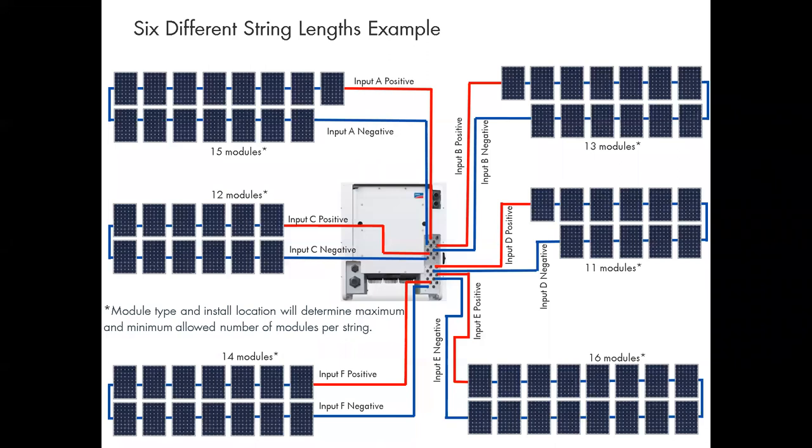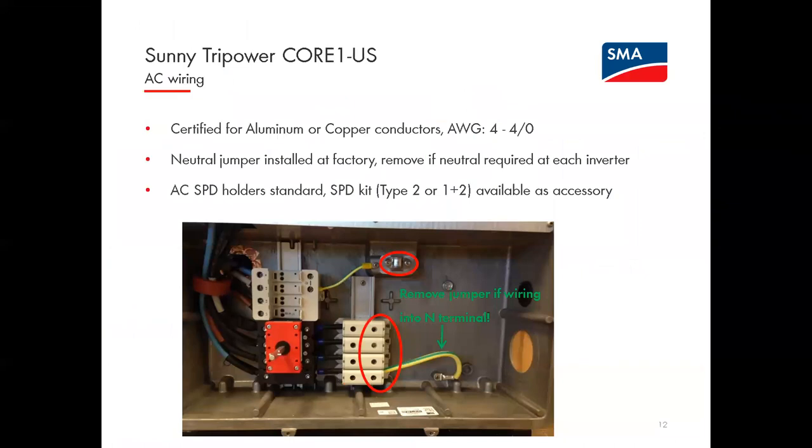Okay, well, let me stick with that theme then. An application question: the inverters provide balanced production on all three phases at 277/480Y. Are you aware of any phase imbalance in aggregated power from multiple inverters after a step down transformer? So that brings up a good point. If, for whatever reason, these are tying into the AC panel to service before you're getting to the utility transformer, obviously those load panels could be unbalanced and that might adjust the voltage of the lines so that they might not be the same. Again, the inverter's exporting balanced current, which means that it might not be exporting balanced power.